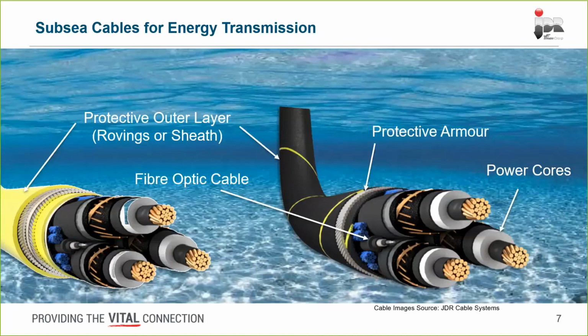These static cables are generally used for wind farms closer to shore in coastal regions, so they're relatively short lengths, with the wind turbine as a fixed structure in the seabed, and the cable connection point close to the seabed, so the cable remains relatively static throughout its life. However, if the cable entrance point on the turbine is a lot higher up, you'll have a hanging length of cable down to the sea floor, which is subjected to current and wave loading, causing it to move a lot, so we need a more robust cable to withstand that fatigue motion while still providing the energy.